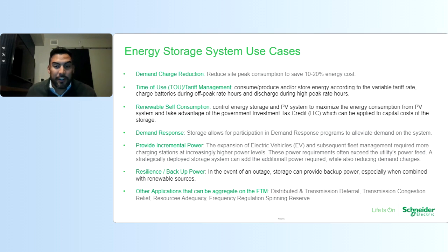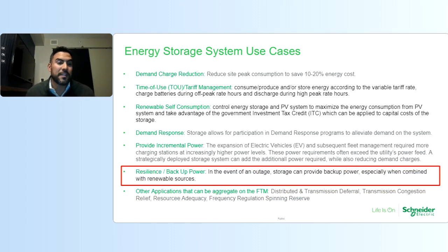And then we're going to go through here, and the main piece here is for resiliency of backup power. So as I mentioned, everything I mentioned above is for grid connected, when the utility is present, right? That's when your energy storage system is making financial sense for your facility. But at the same time, when you experience an outage, you would also want to use that energy storage system for some type of backup power or resiliency. So in the event of an outage, you can use this energy storage system to provide power to emergency loads in your facility and also non-emergency loads, depending on the type of facility you have.